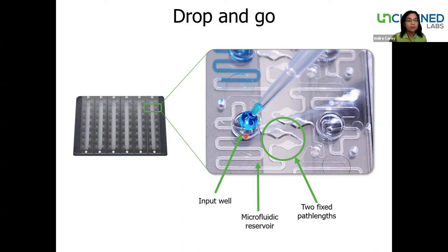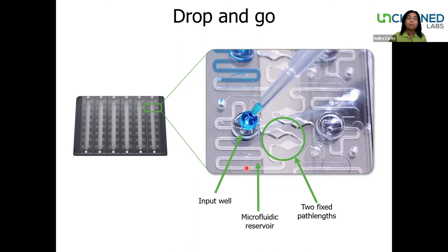The unique microfluidic circuits that are molded into Lunatic plates and chips ensure there's no cross-contamination or evaporation. Once the sample is loaded, it's pulled into the reservoir area by capillary action. When the sample hits a hydrophobic point, it stops. At this step, the sample can actually sit for up to two hours before reading with no evaporation. After the plate is loaded into the instrument, the empty microcuvettes are read — that removes any absorbance contribution from the plastic. A pump then applies a small vacuum, which moves the samples into the microcuvettes for reading.